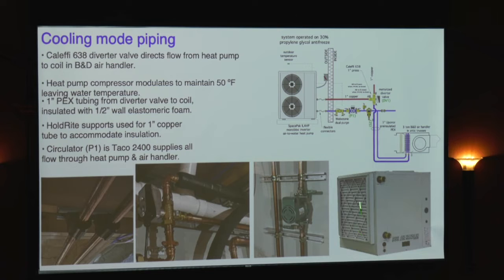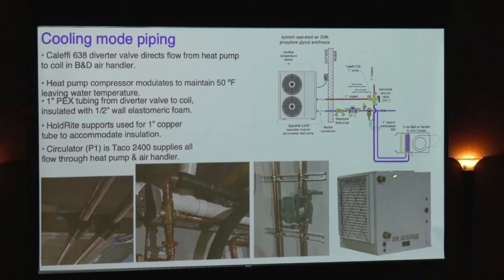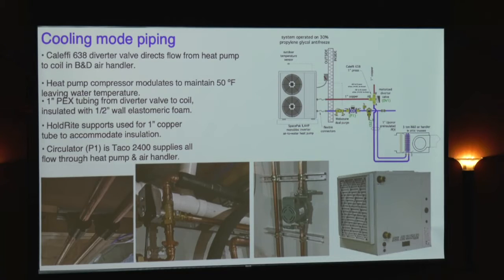That's what the air handler looks like. It's from a company down in the States called B&D Manufacturing. They're big in the geothermal market. They make the pumping stations. But nice big coil. That unit is basically a 2-foot cube. It's 2 foot high, 2 foot wide, 2 foot deep. And there's an ECM blower in there. And as I mentioned, the manufacturer actually did a little custom programming for us so we could run that at 150 CFM or 1200 CFM, just 2 different wire tappings.